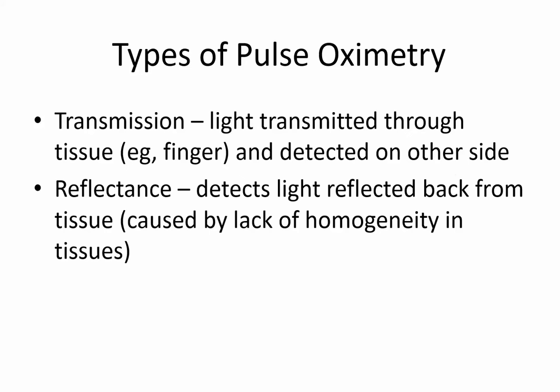There are two different types of pulse oximetry, transmission and reflectance. In transmission pulse oximetry, the light is transmitted through the tissue and detected on the other side. That's the form that we use most commonly when we're putting a probe on the finger. Reflectance oximetry detects light reflected back from the tissue, and it's caused by lack of homogeneity of the tissue.